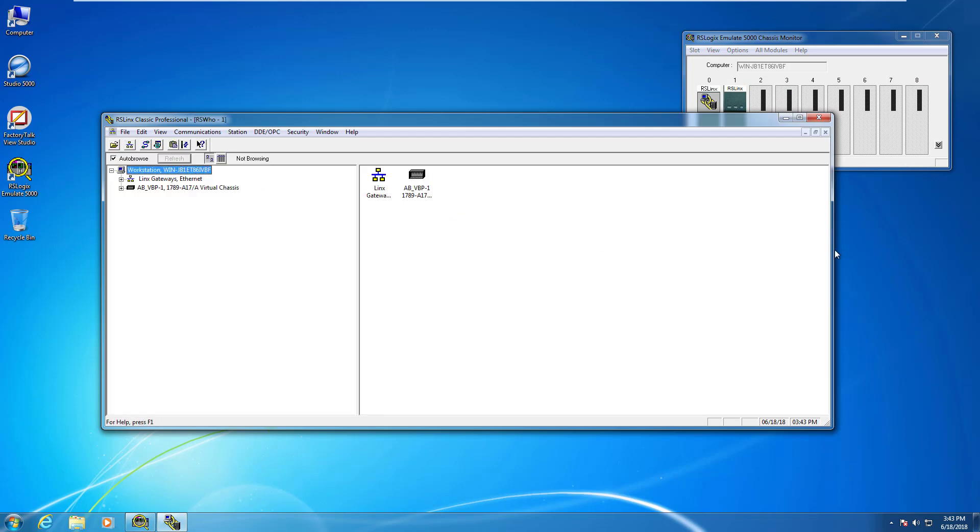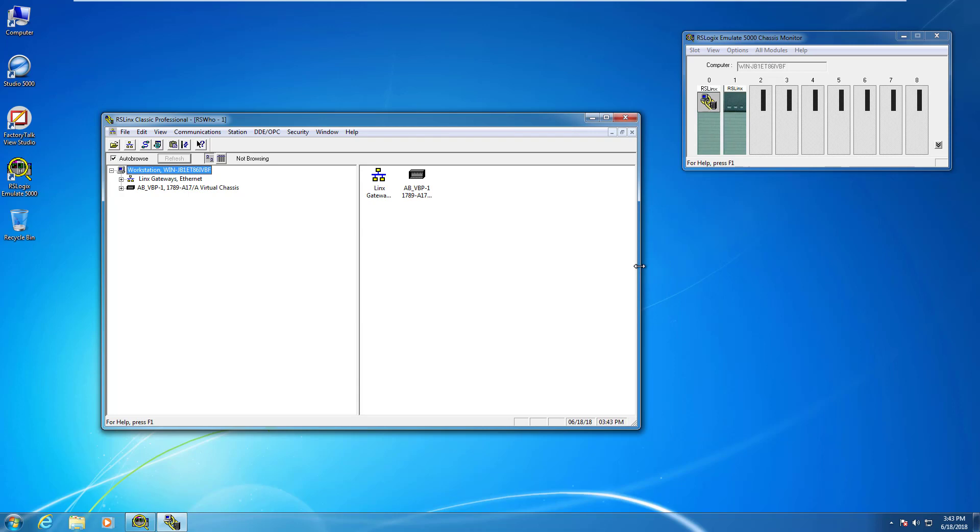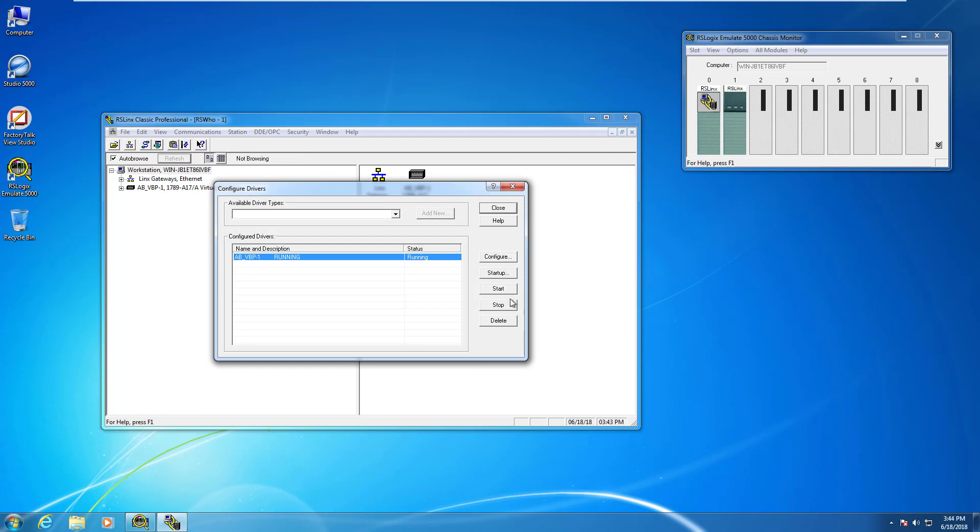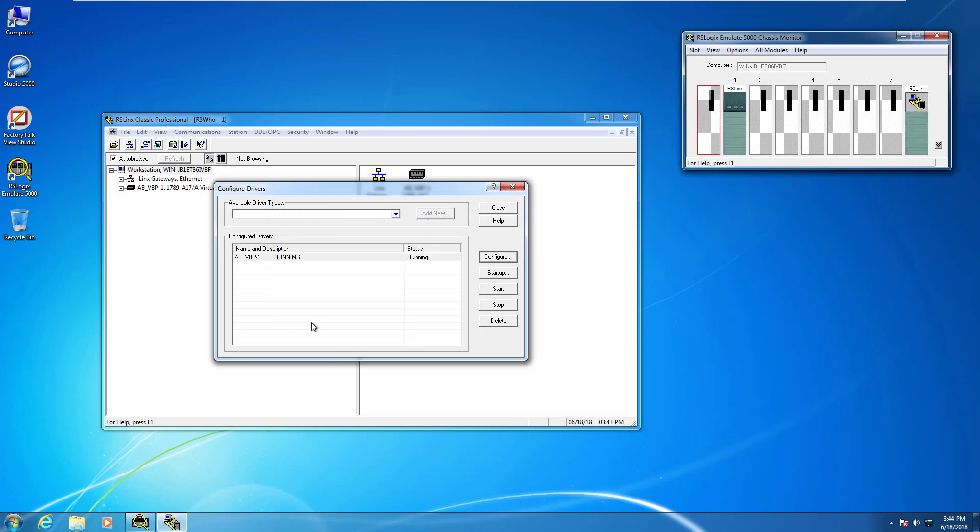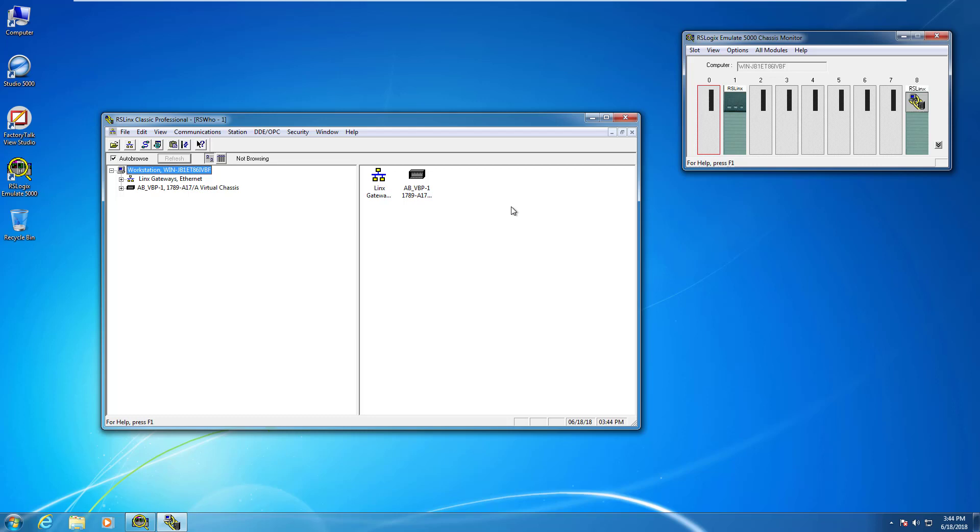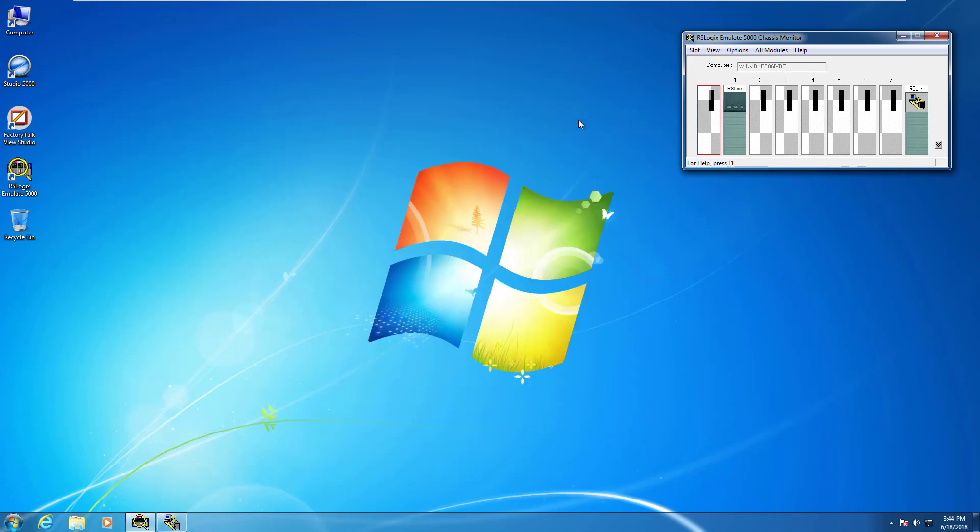We're going to launch RSLinx. I'm going to go to communications, configure drivers, and stop this driver. Then I'm going to configure it. I do not want this RSLinx module in slot zero. We're going to move it right to the end, slot number eight. There it is. Click okay. Now you can see slot zero is available and we've moved the RSLinx module to slot eight. So that's really what I wanted to do here.